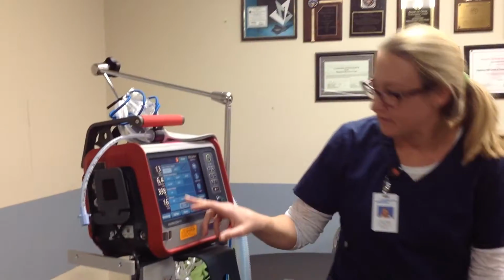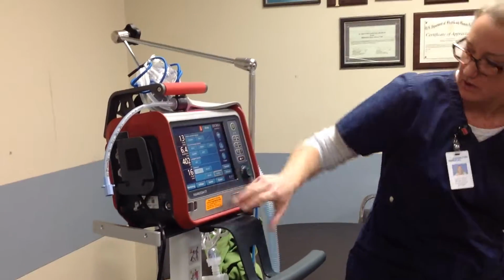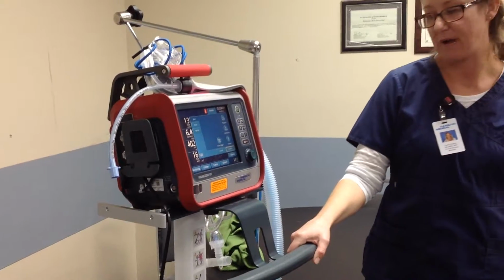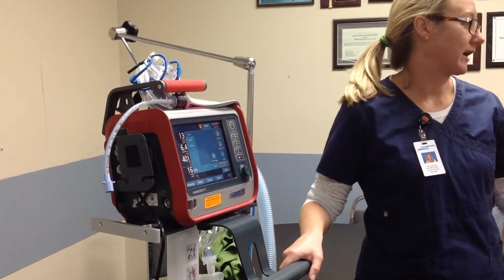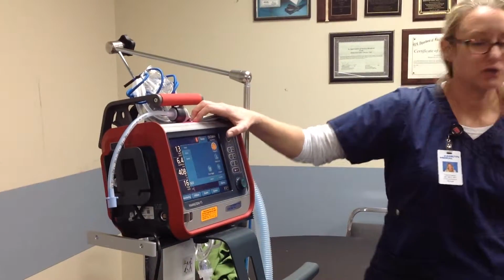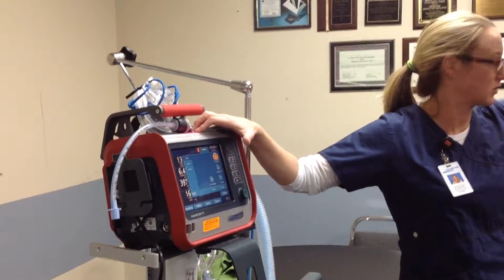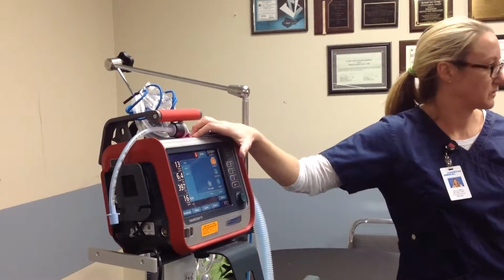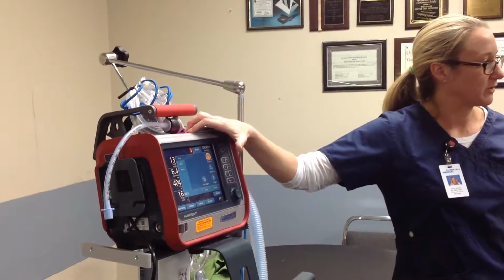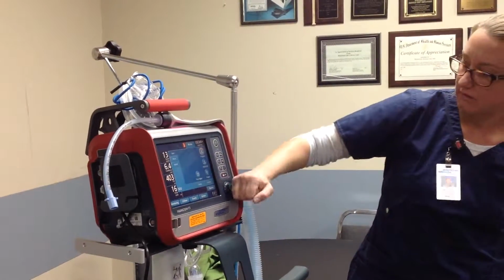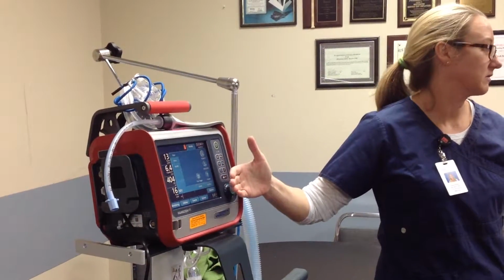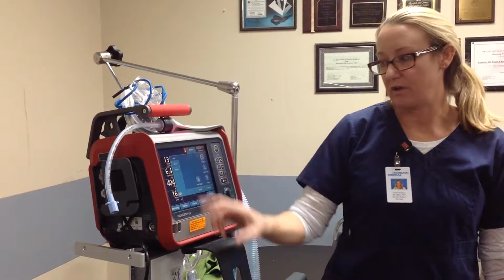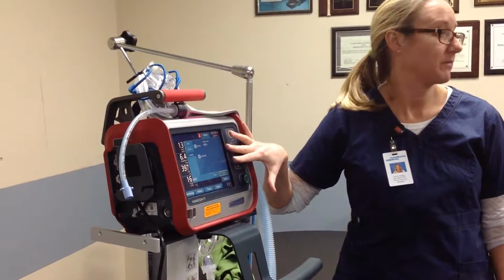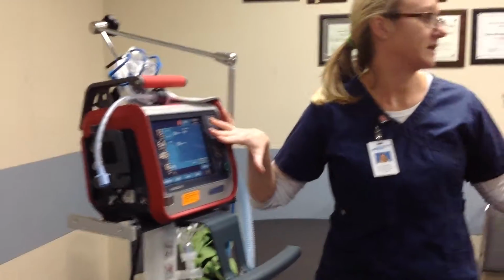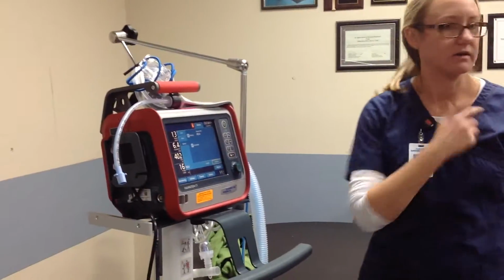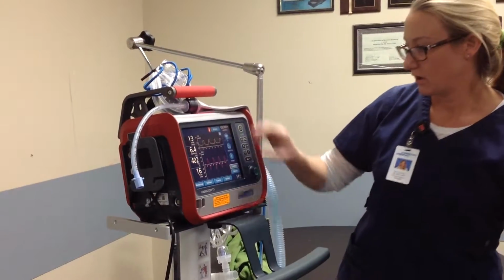Okay? And then your last row here are your non-invasive modes. NIV is BiPAP without a backup time or a backup rate. So you set pressure support as your IPAP or your inspiratory pressure, and then PEEP CPAP, that's your expiratory pressure. So a high pressure and a low pressure that they're breathing at. You can also turn pressure support off, and you could have this run as a CPAP machine. Okay? The only thing here is that unless you set an apnea timer for a backup, you don't have a backup rate kicking in to say, hey, breathe, okay? Nothing that's tapping on their shoulder. Okay?